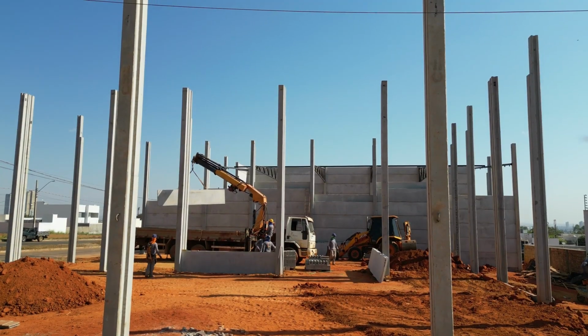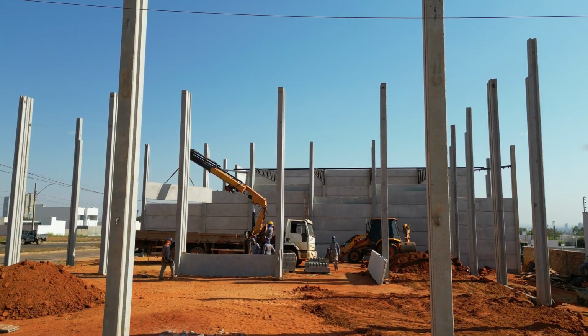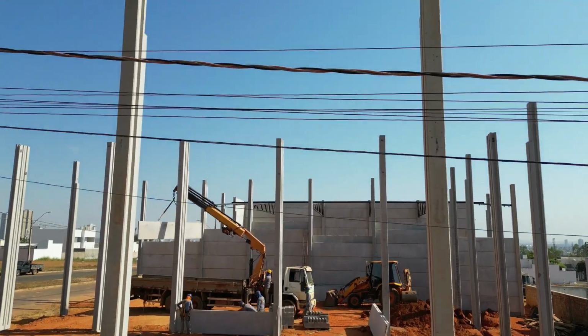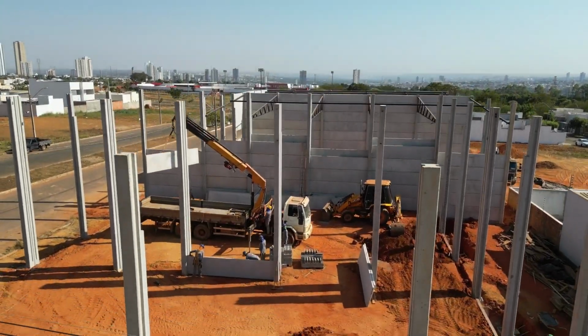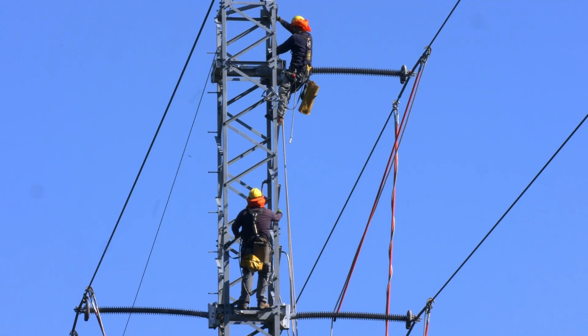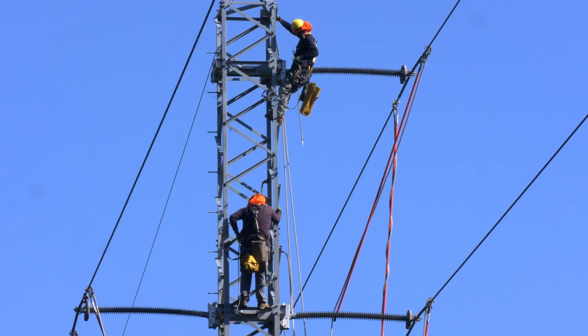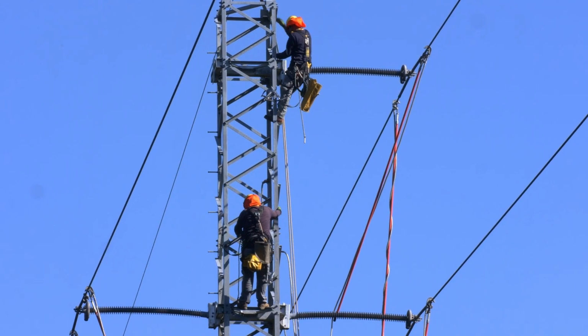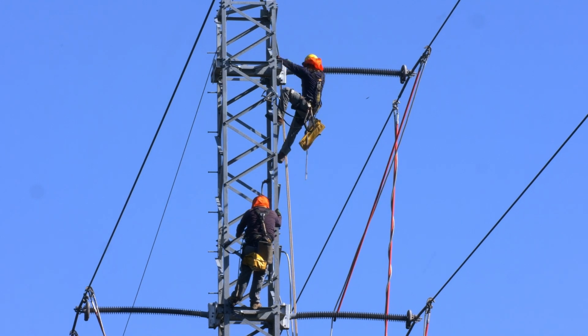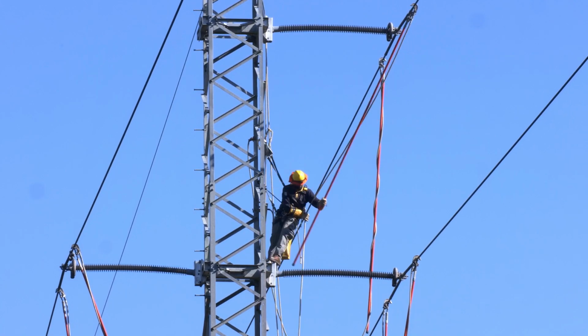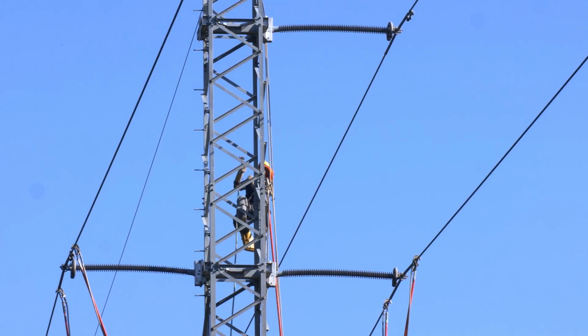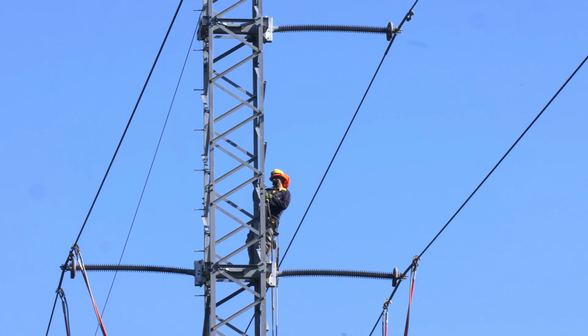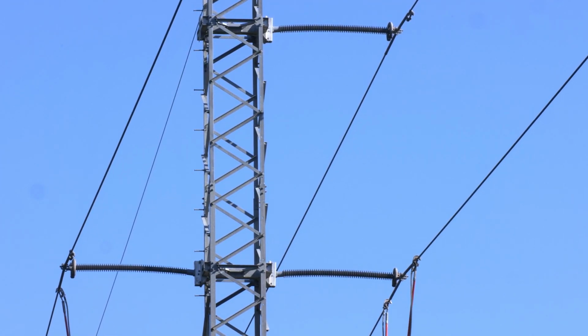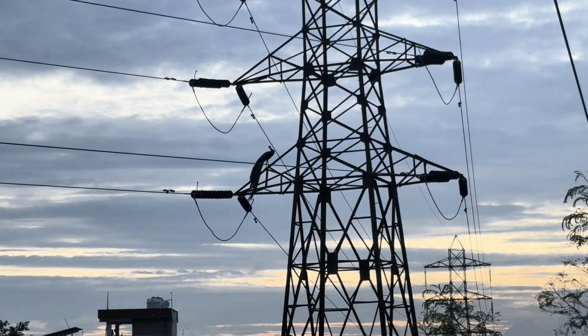This voltage conversion is performed by transformers. A transformer is a device that uses electromagnetic induction to increase or decrease voltage. It contains two coils of wire placed close together. When alternating current flows through one coil, it creates a magnetic field that induces voltage in the second coil. The ratio between the number of turns in each coil determines whether the voltage increases or decreases.